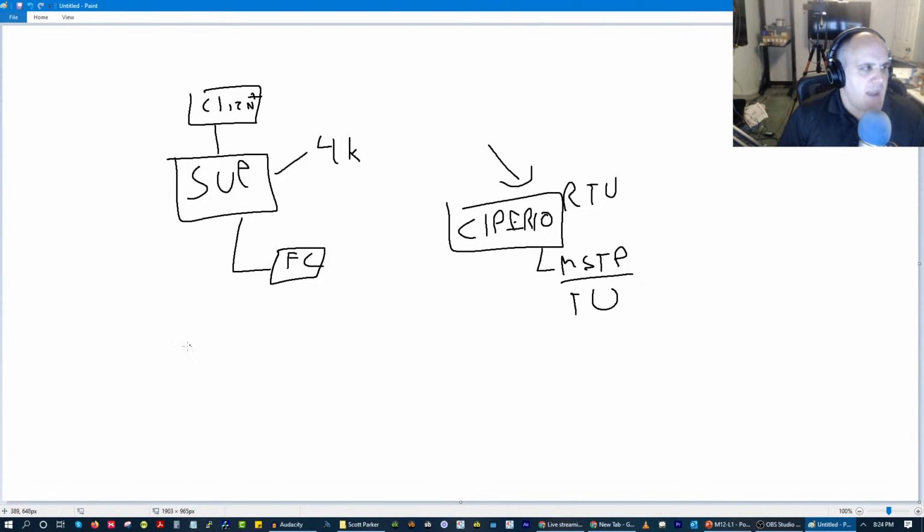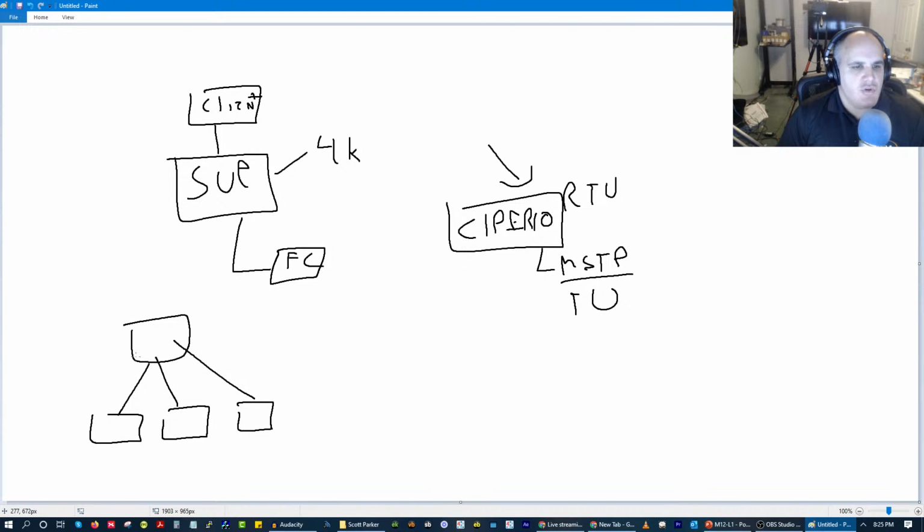But there are 3 IP architectures that we can implement. So with all of these IP controllers, let's say I have 10 rooftops. I could have 10 different controllers all home run to a switch. And that's going to be rather expensive. I'm usually paying per port to IT in order to utilize their switches. So that's going to get a little bit pricey.